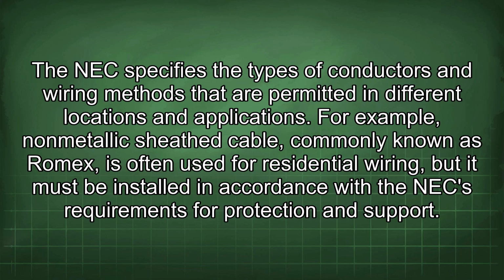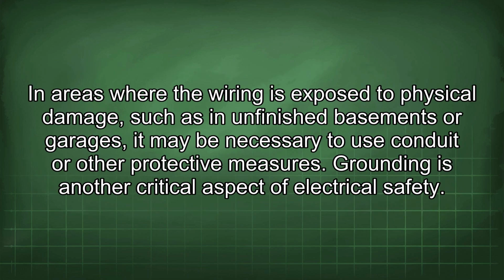For example, non-metallic sheath cable, commonly known as Romex, is often used for residential wiring, but it must be installed in accordance with the NEC requirements for protection and support. In areas where the wiring is exposed to physical damage, such as in unfinished basements or garages, it may be necessary to use conduit or other protective measures.